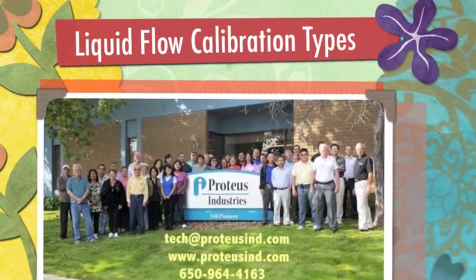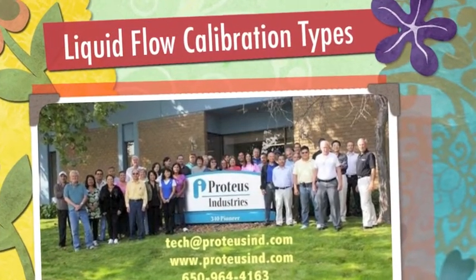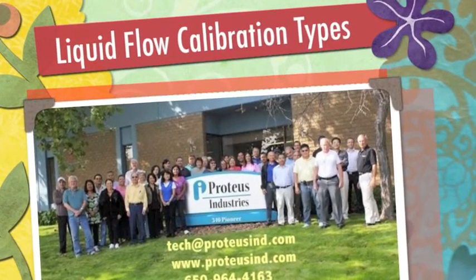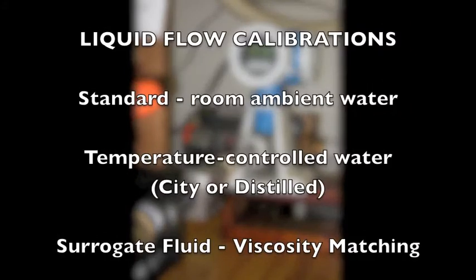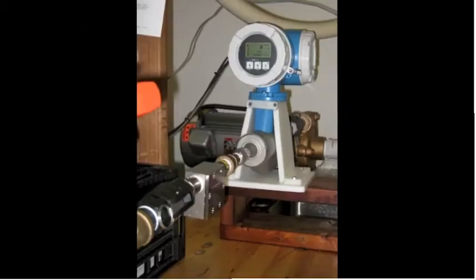Here are the liquid flow rate calibration types provided by Proteus Industries. Flow rate is calibrated in either room temperature ambient water, temperature controlled water, which is either city water or distilled water, or a surrogate fluid so that the viscosity can be matched.